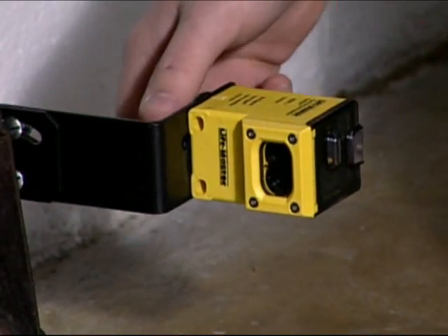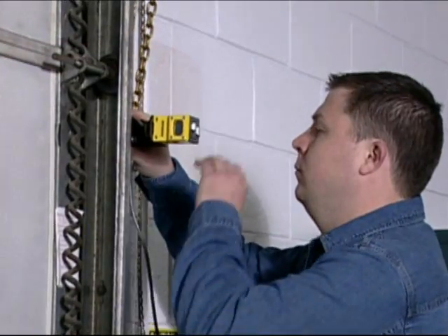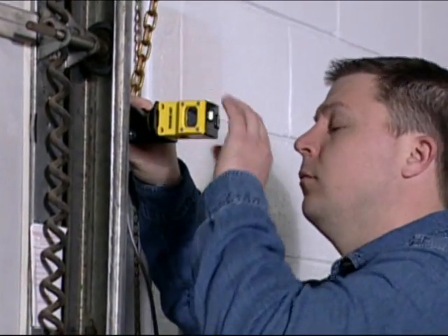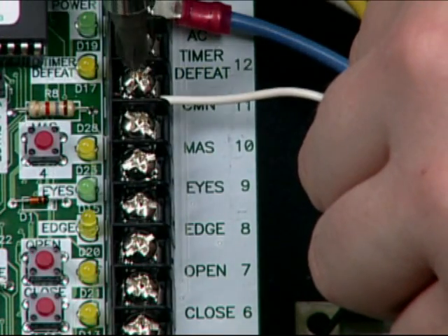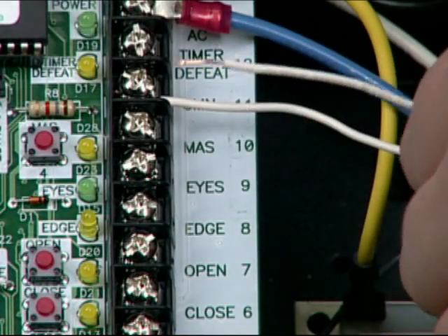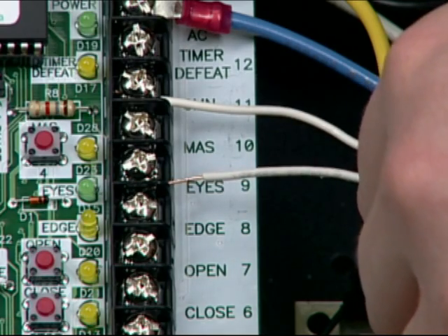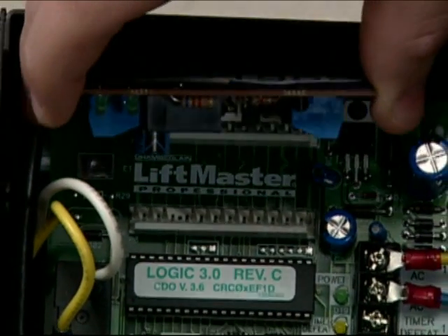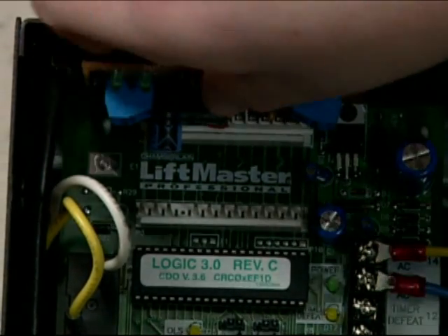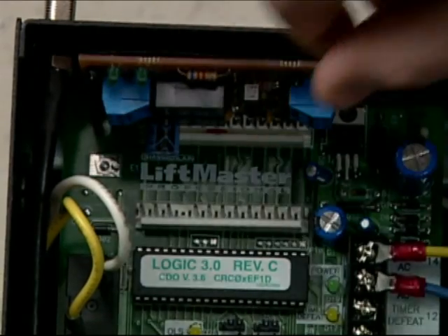In certain applications, it is required to have 2 sets of photo eyes. Model CPS-3 and Model CPS-L should be used. The CPS-L is directly connected to the low-voltage terminal strip. In the CPS-3, the photo eyes included are directly connected to the CPS-3 option card. The option card is then plugged into the logic board.